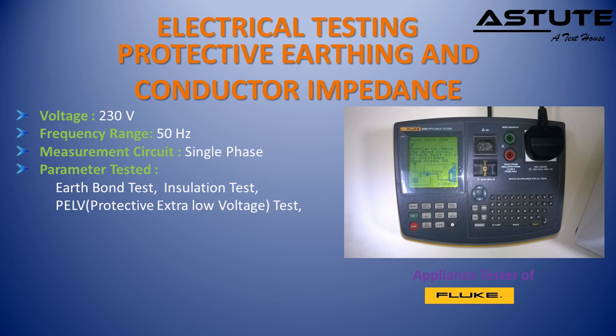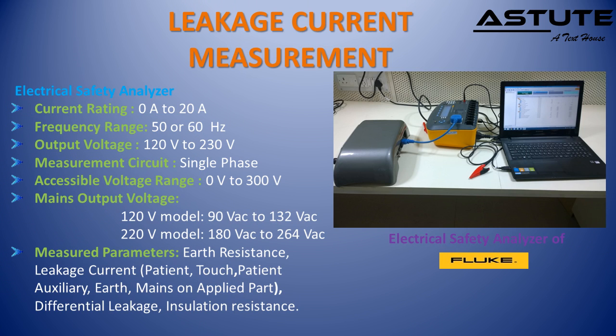For protective earthing and conductor impedance testing, we use Fluke appliance tester. This tester is used to carry out insulation test of 500 volt DC and earth bond test at 200 mA and 25 ampere. For leakage current measurement, we use ESA620 electrical safety analyzer of Fluke. We measure earth resistance, leakage current types that are patient leakage current, touch leakage current, patient auxiliary current, earth leakage current, mains on applied part, differential leakage and insulation resistance.